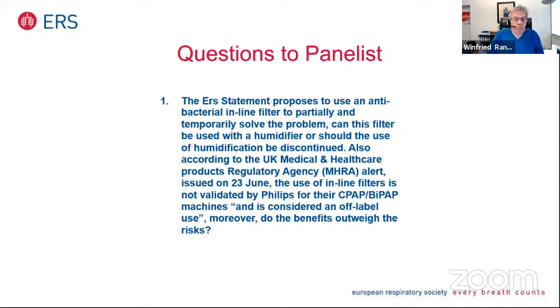We have to state that we do not have precise data on the efficacy of the filters, but what we can say is that the particles which have been found were bigger than 7 to 8 micrometers, and the filter eliminates particles down to a limit of 2 micrometers. So that means the filters, to the best of our knowledge, should be safe regarding the particles. So that's one important message. Second, yes, we have to stop using humidifiers when using the filters, because humidification will lead to closure of these filters, and therefore the resistance will increase and might lead to ineffective treatment.